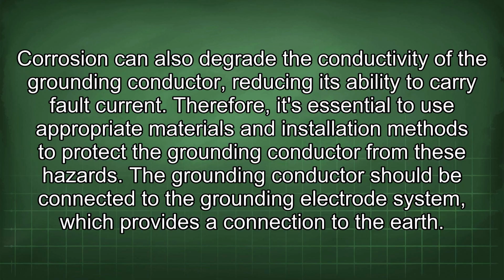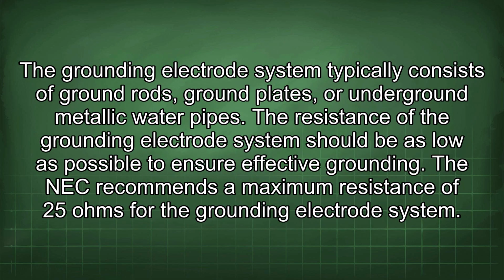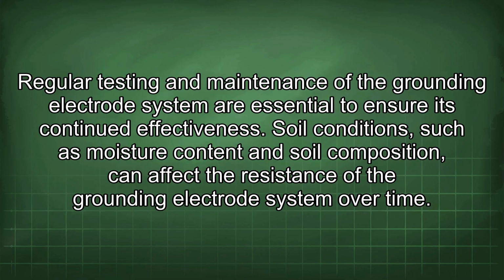The grounding conductor should be connected to the grounding electrode system, which provides a connection to the earth. The grounding electrode system typically consists of ground rods, ground plates, or underground metallic water pipes. The resistance of the grounding electrode system should be as low as possible to ensure effective grounding. The NEC recommends a maximum resistance of 25 ohms for the grounding electrode system. Regular testing and maintenance of the grounding electrode system are essential to ensure its continued effectiveness. Soil conditions, such as moisture content and soil composition, can affect the resistance of the grounding electrode system over time.